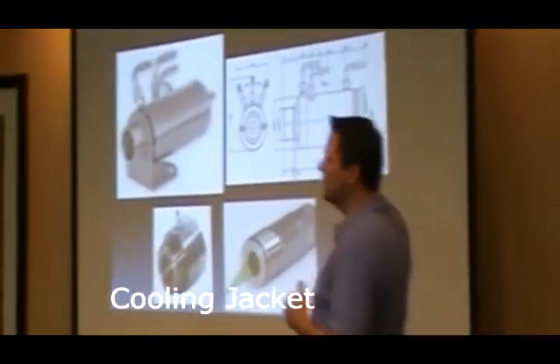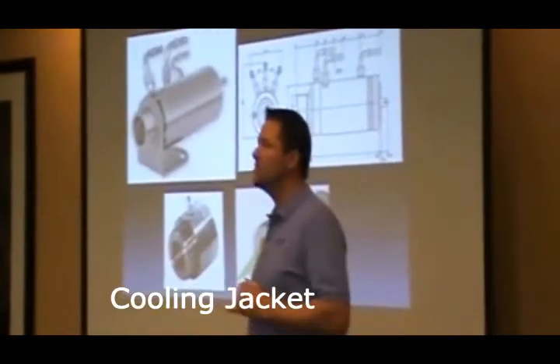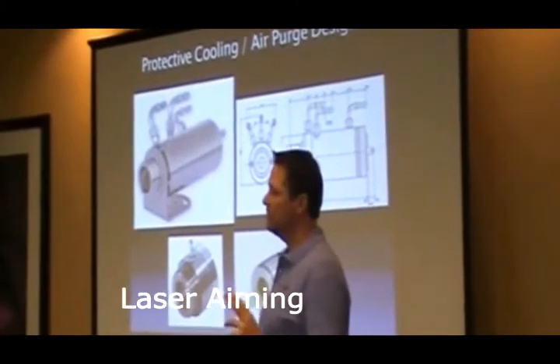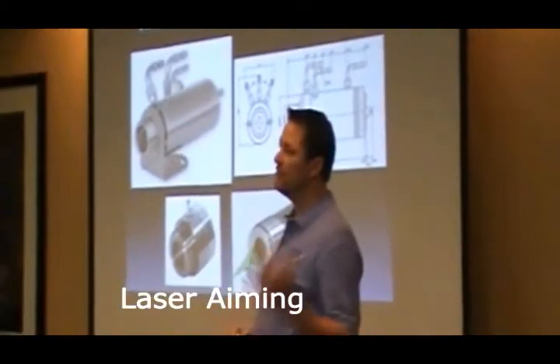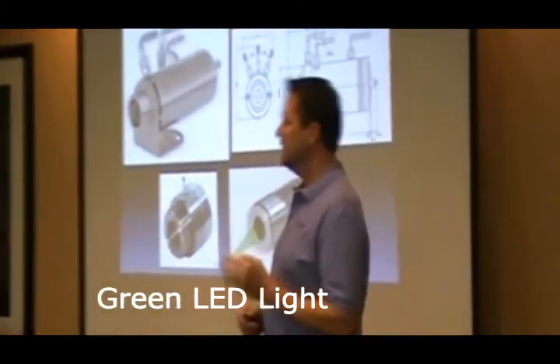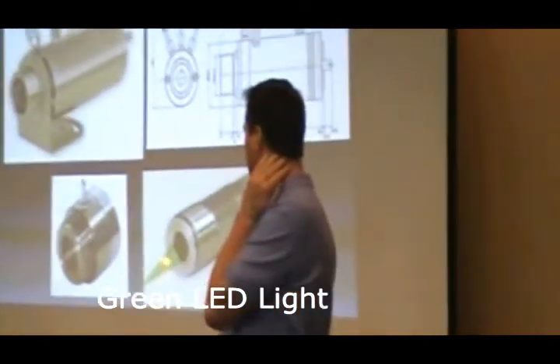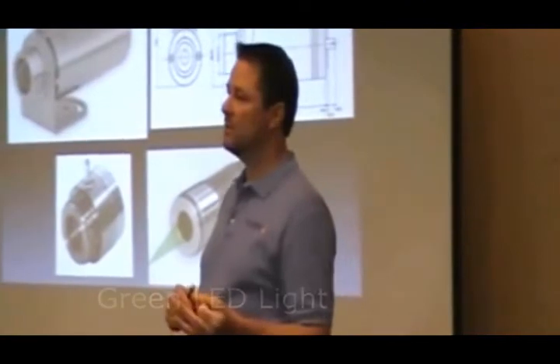These sensors, the DS and DG44 series, offer laser aiming. It's a single laser, or they can have a green LED light inside. That's used for maybe up to five feet, but that green LED light shows you the exact spot size of the target visually.